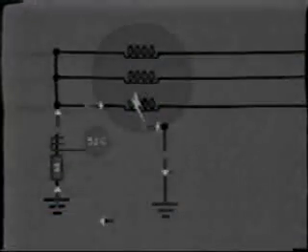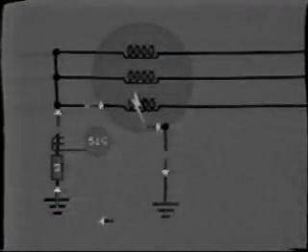Ground fault current will flow from the faulty winding to the stator laminations, then to the frame, which is connected to the grounding mat. From here, it will flow up the generator neutral, so completing the path for circulation. A CT can be connected into the neutral to measure this flow of current. The CT secondary will be connected to a time over current ground relay, device number 51G. More commonly used, however, is an inverse time over voltage relay set to pick up at about 10 volts.